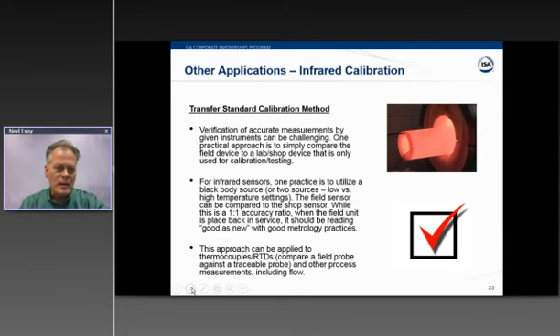And on this first bullet, verification of accurate measurements can be challenging for any instrument. And in general, if it's something that's difficult or tricky, like a flow measurement, or in this case, infrared, can you find a way to just simply compare the field sensor against a similar sensor or device that you maintain in your shop or your laboratory? So the unit that stays in the shop or laboratory, it's not getting abused, it's not being exposed to extreme temperatures and weather. So it should not drift like a field sensor might.